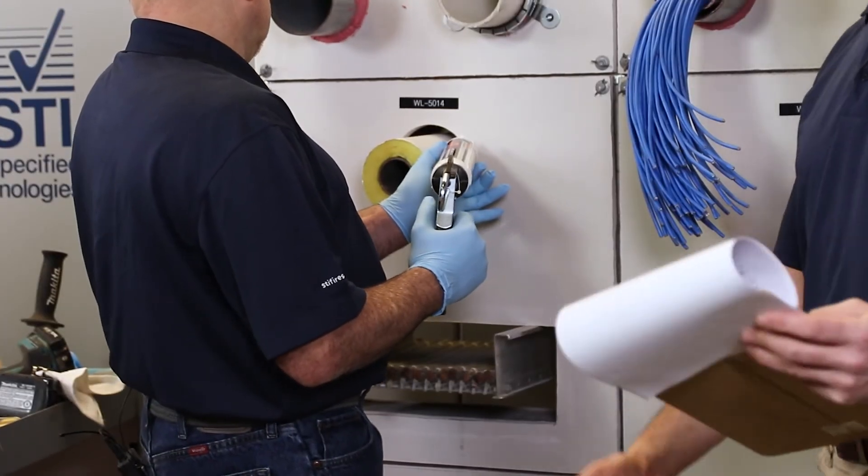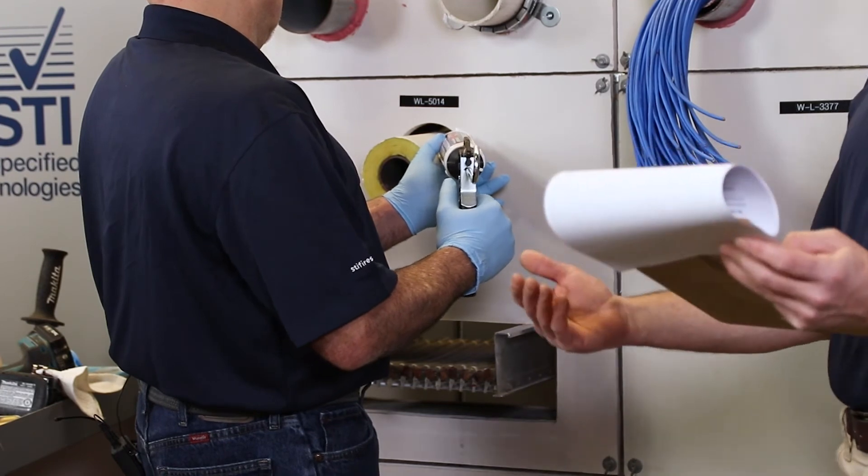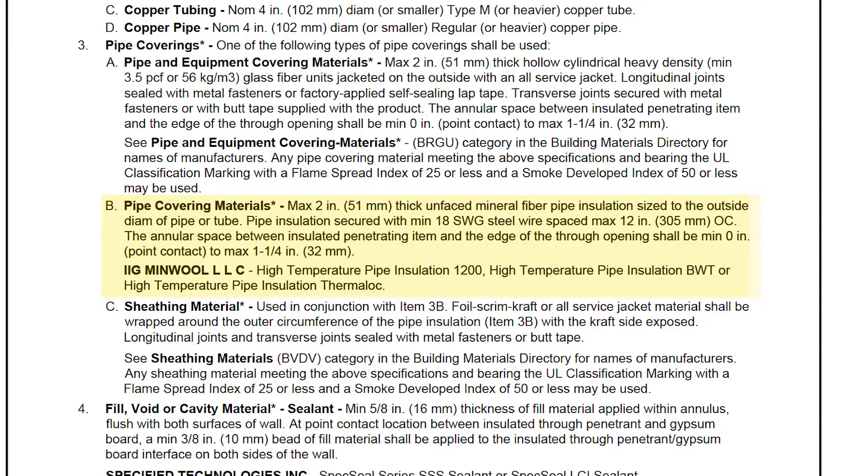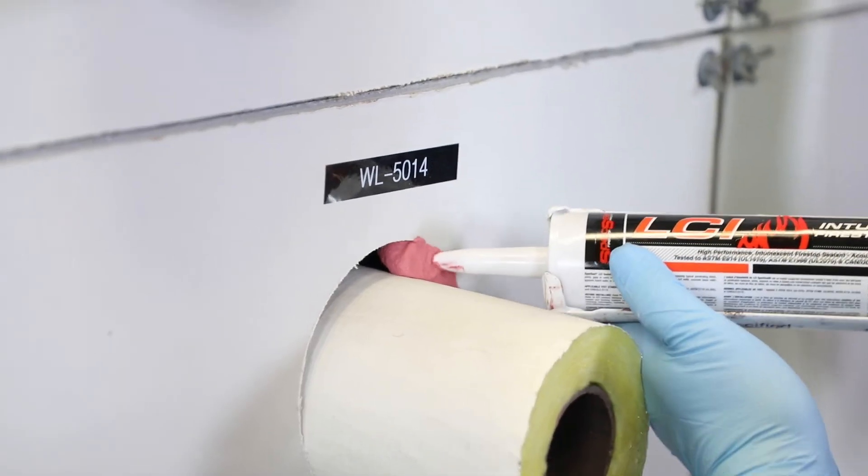We'll check the pipe coverings here. Obviously you always need to check everything within a system. This pipe covering is the glass fiber insulation. We're allowed up to two inches. This is a caulk only system.